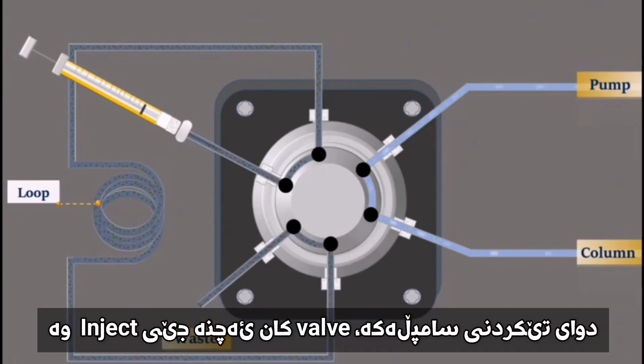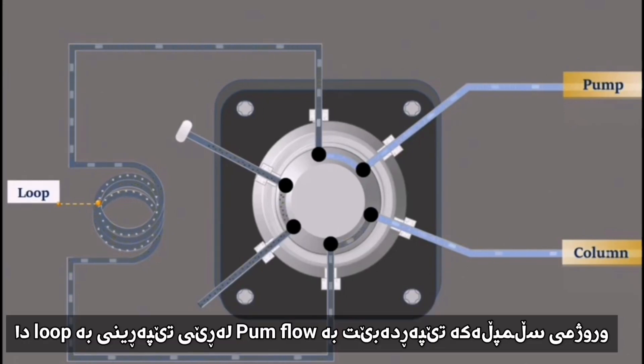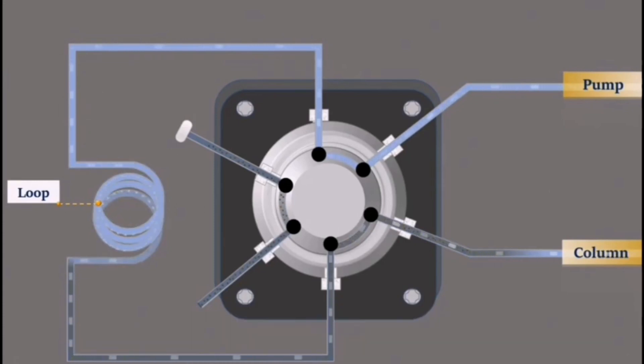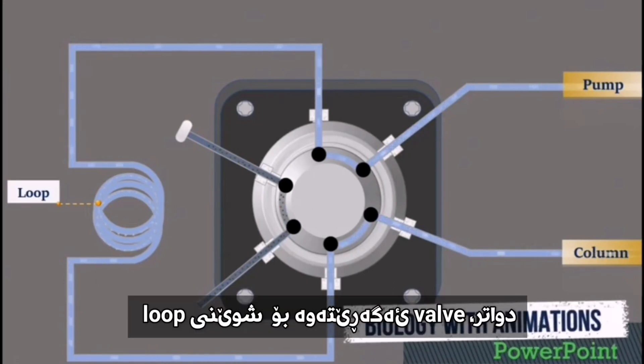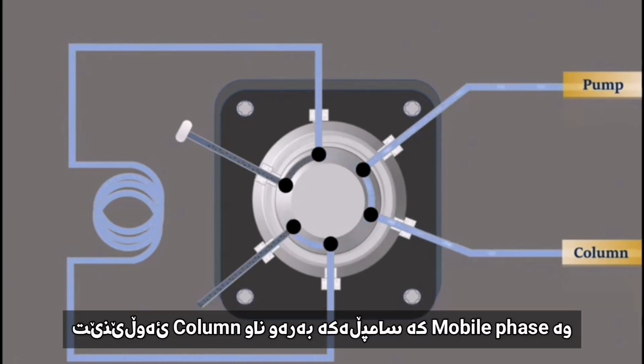After loading the sample, the valve is switched to the inject position. The flow delivered by the pump flows through the loop, forcing the sample ahead of it, flowing to the column. Then the valve returns to the load position, and the mobile phase moves the sample through the column.